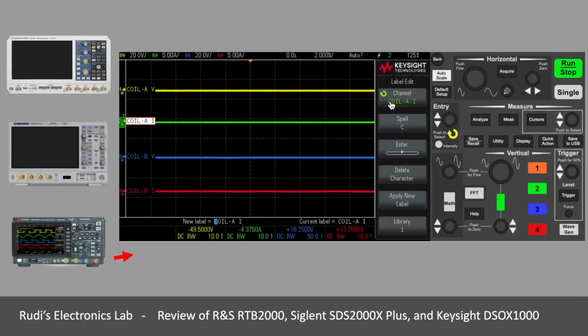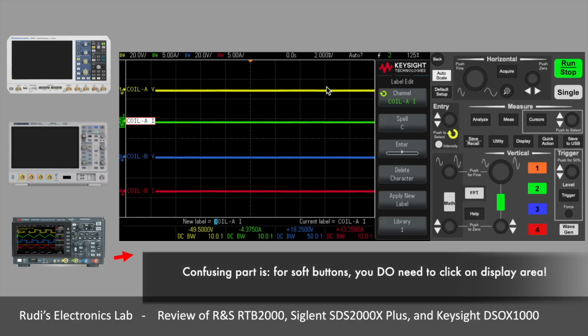Now this is where I often make a mistake, because if I'm in the web interface and I'm trying to click here, I cannot do that because this is not clickable, it's not supposed to be part of the I/O interface of the device.